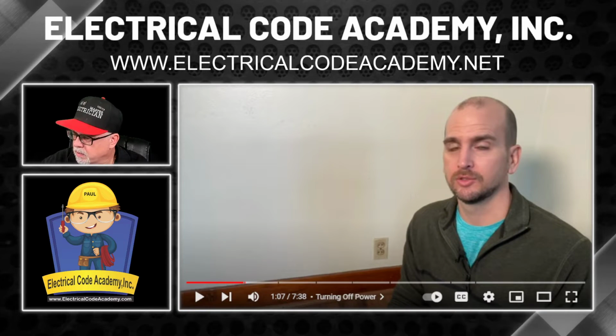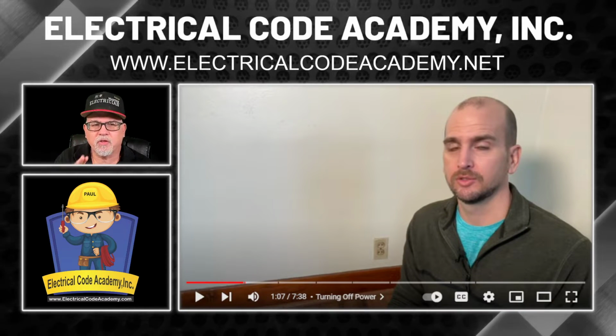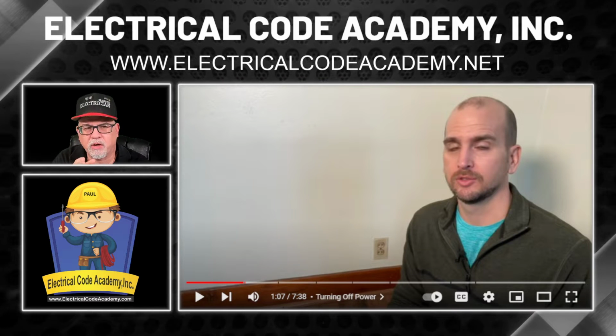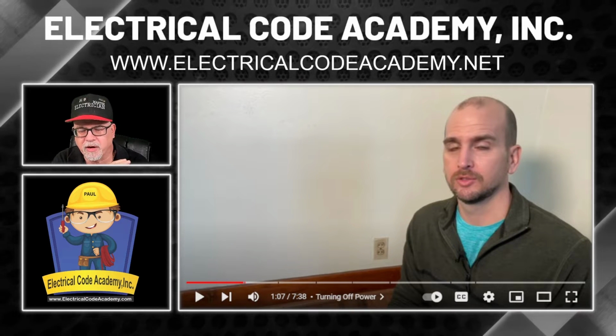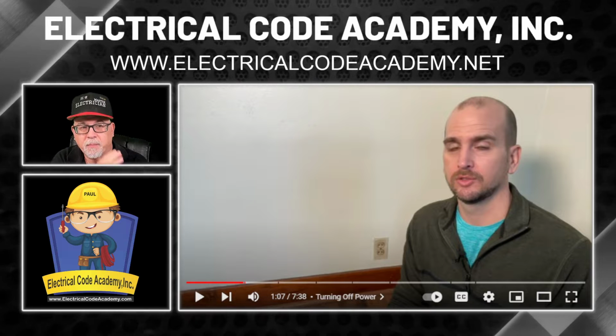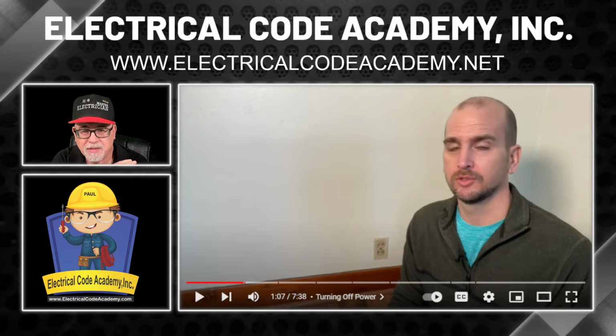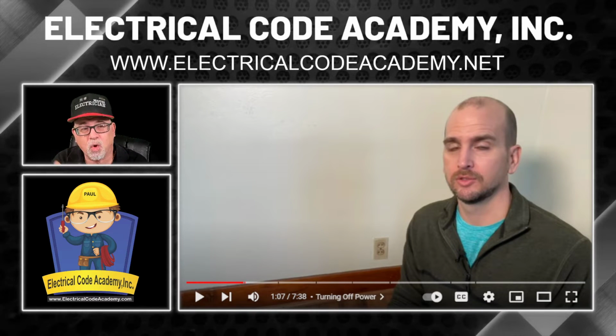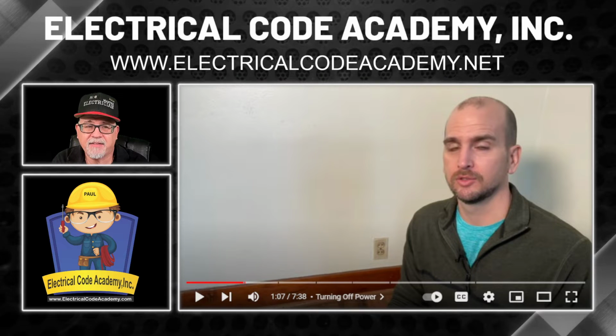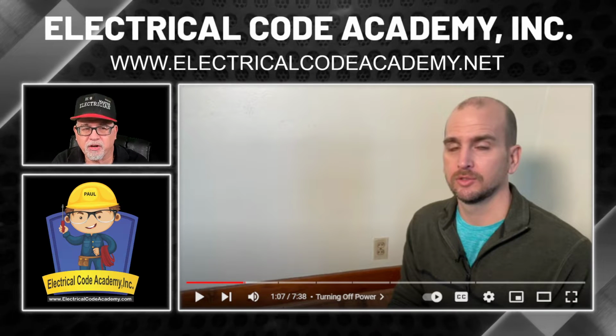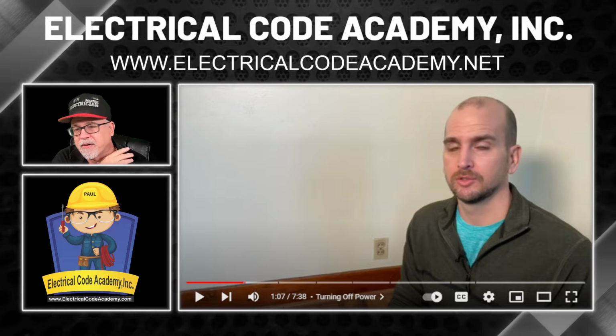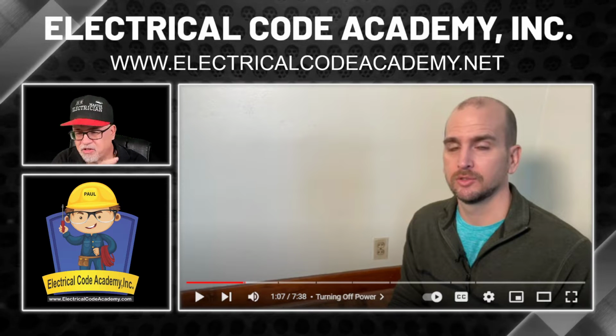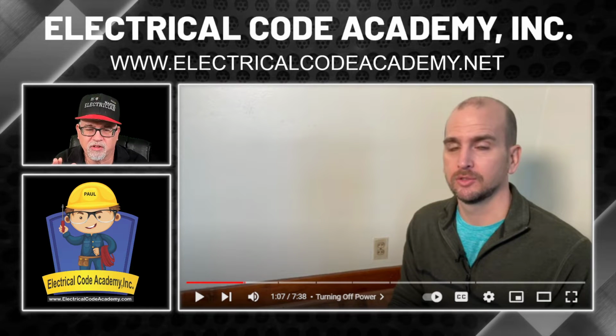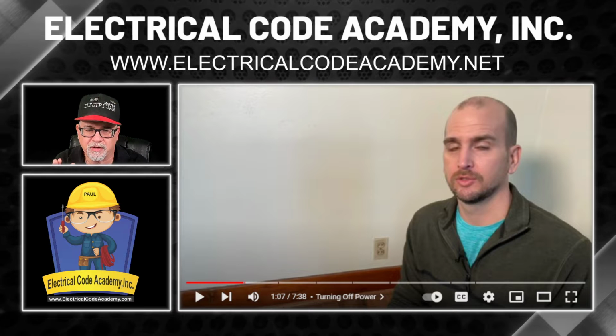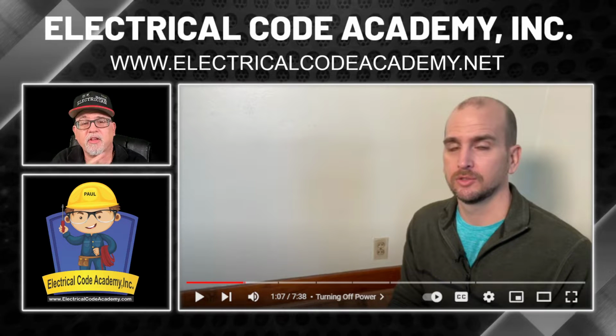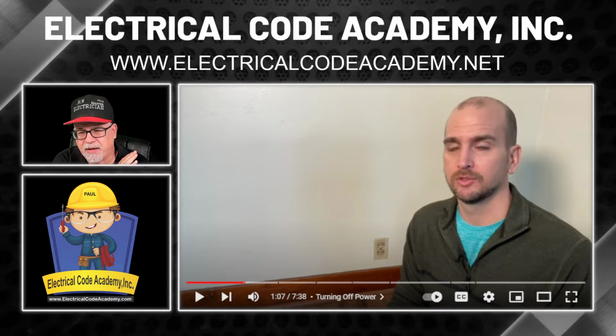So now remember, there's also the ability, let's say this is an older house and there was a service upgrade or a service change. If the panel is newer, but the branch circuits are existing and it's older, then you might have the option to put a GFCI circuit breaker in the panel and it protects everything downstream and achieve this goal of being able to change out all these receptacles to three prong instead of two prong. Okay, so there are other options, but that only works if you have a panel that can accept it.